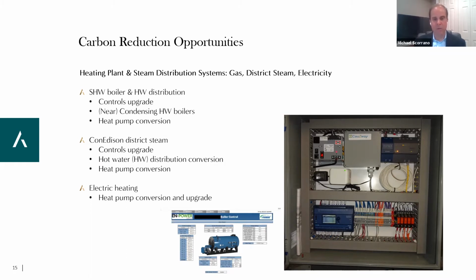And the picture there is just something we did for one of the buildings. We put in a brand new boiler control system, then we were able to monitor it 24/7. It gives alarms, notifications, and also allows us to adjust parameters remotely. If we see the boilers are getting out of whack, we're able to adjust things to make things a little bit better. And the good thing about controls is there's rebates associated with them as well.